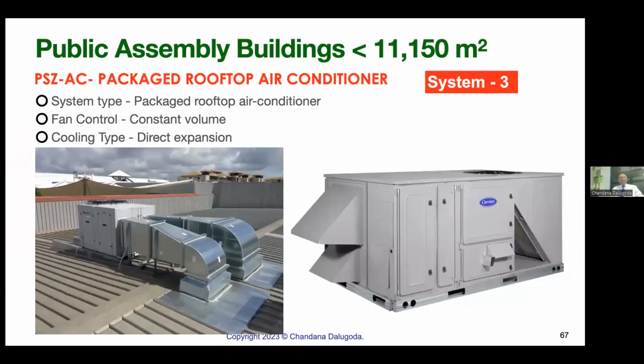For public assembly buildings that are 11,000 square meters and below, those are like shops, small offices, classrooms, something like that, better equipment is rooftop package units. People don't understand in Sri Lanka, this is the most efficient air conditioner available because these are factory tested, with fresh air entrance, exhaust, all inbuilt with the economizer. Night purge can be done. One single source, factory tested. You need to supply only power supply, condensate drain, and supply return ductwork.